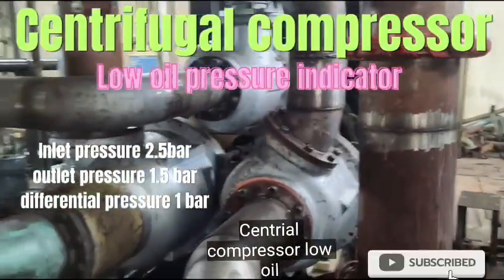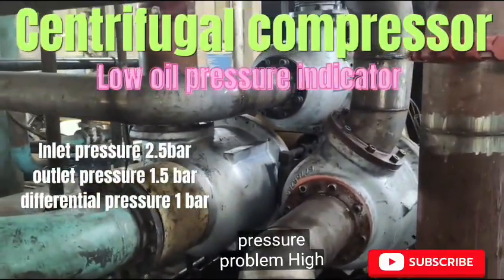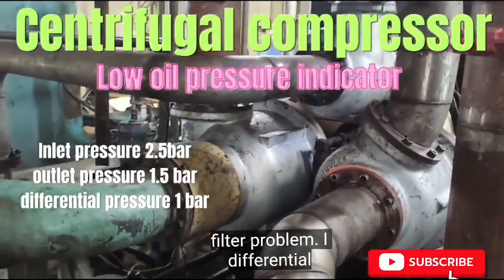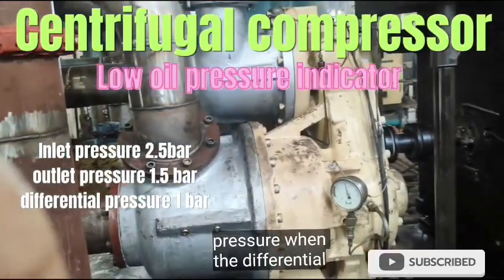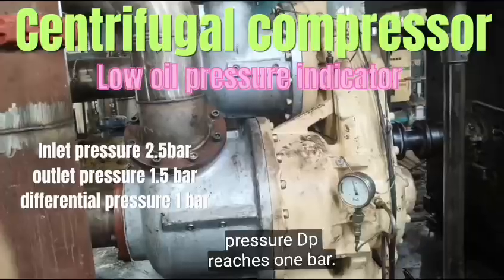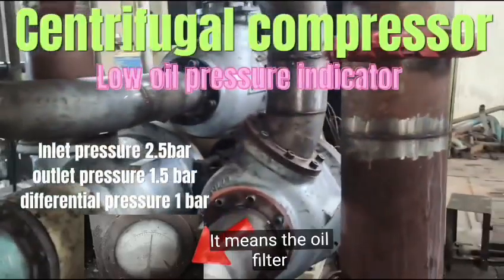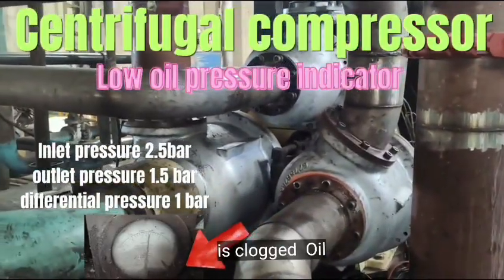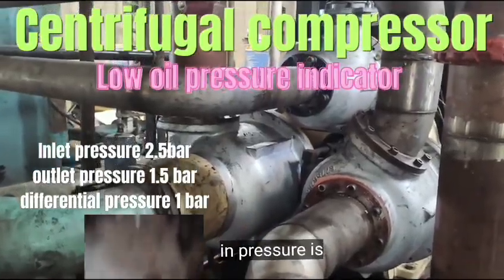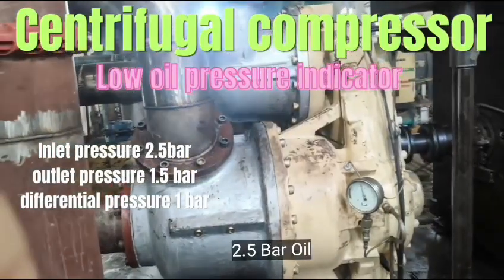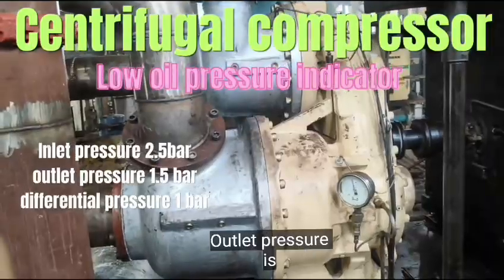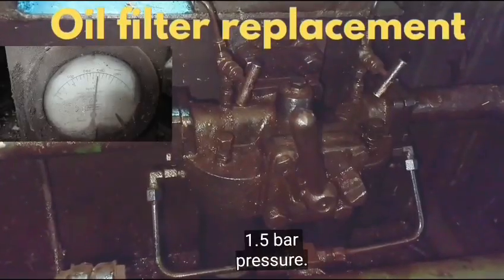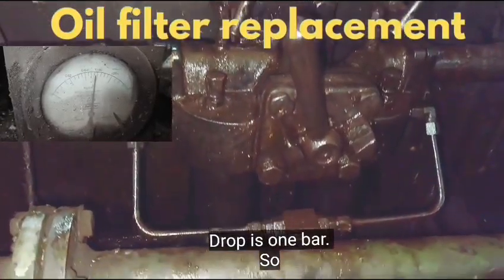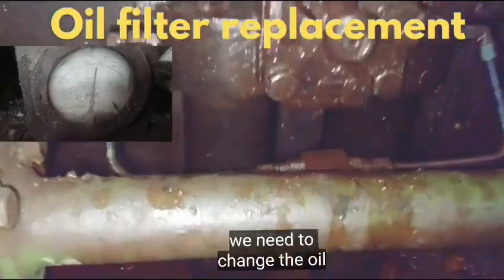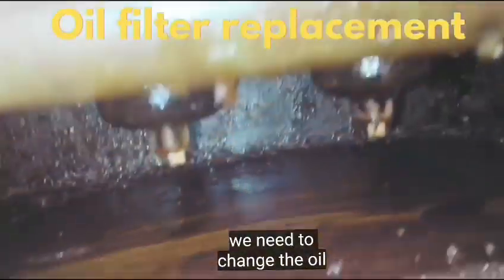Centrifugal compressor, low oil pressure problem, oil filter problem, high differential pressure. When the differential pressure reaches 1 bar, it means the oil filter is clogged. Oil inlet pressure is 2.5 bar. Oil outlet pressure is 1.5 bar. Pressure drop is 1 bar. So we need to change the oil filter.